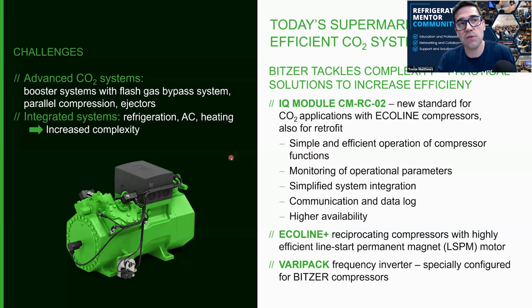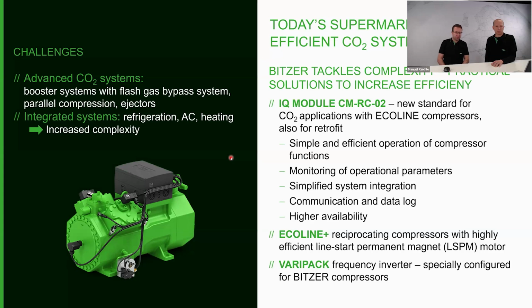But have you ever seen, with some of the manufacturers you may have worked with, where they have to add something to keep the rack running? Because even with just the VARISTEP running at minimum, the load is still too low. Have you ever seen that? With the VARISTEP, not so far, because we can really go quite low in capacity.